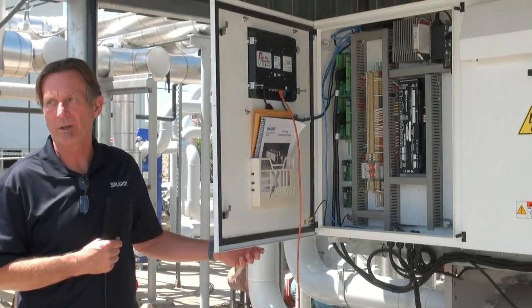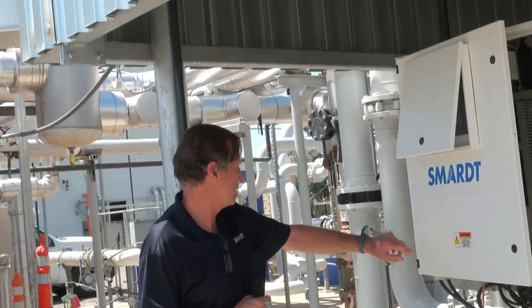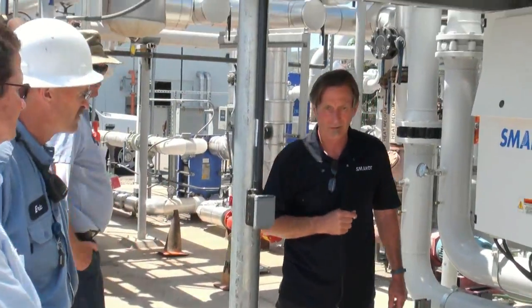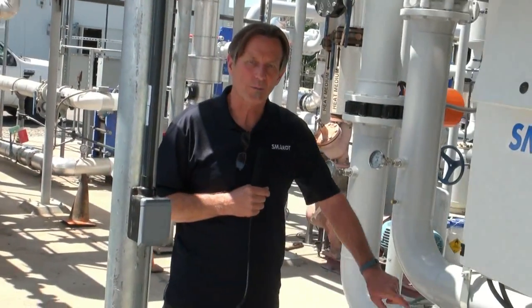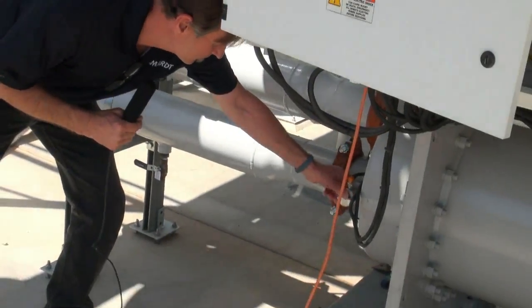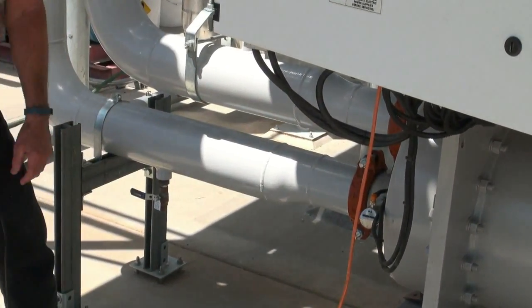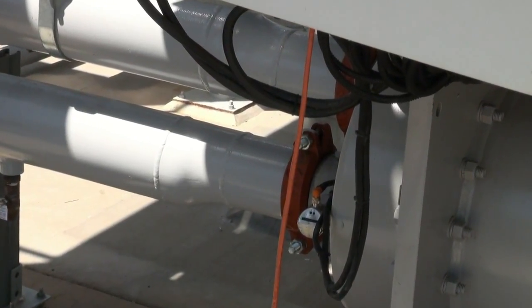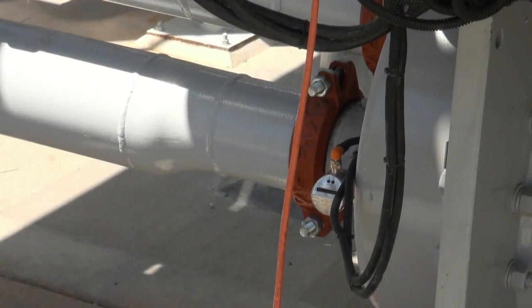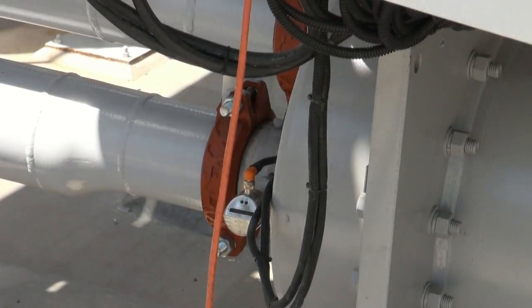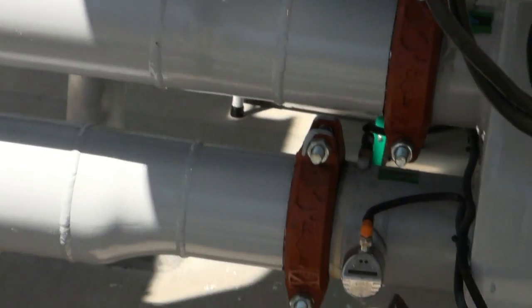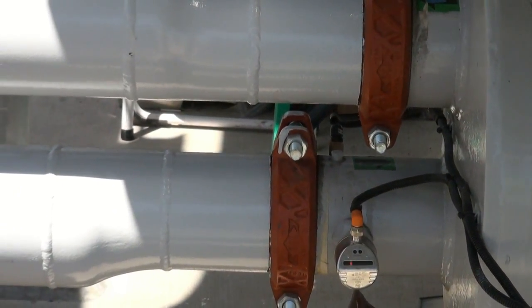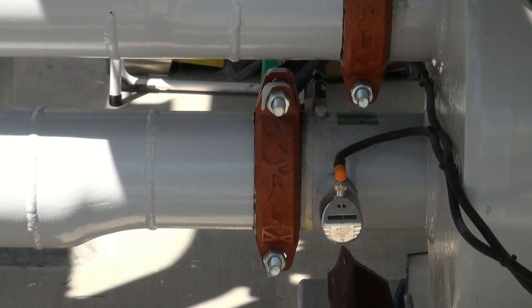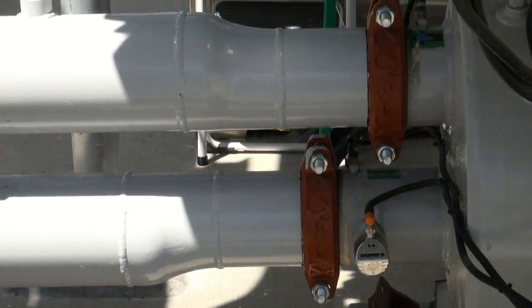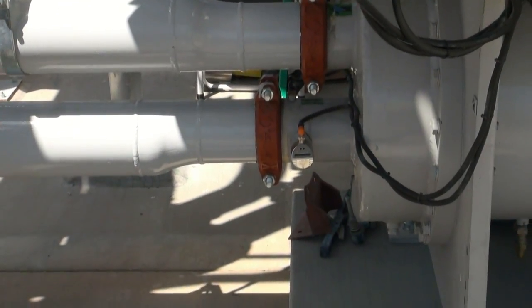We want to walk around the chiller a little bit, and I'll show you the flow switch. This is typical of both the chilled water and condenser water. You can get a close-up of the flow switch. It's a digital flow switch, actually analog and digital, so you'll have a number of LEDs that march across your analog indicator. But it's actually proof of flow, yes or no, so it's basically a digital output, and you get a nice visual reference.